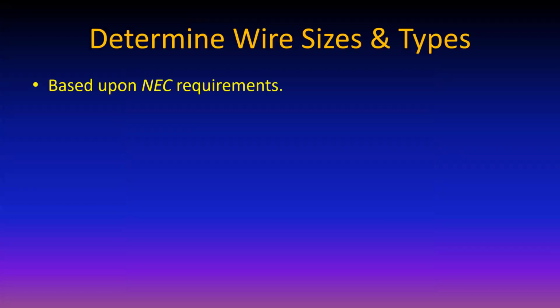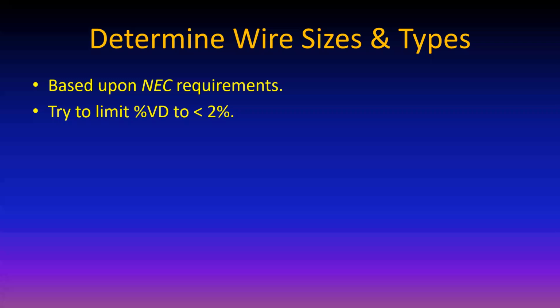Okay, wire sizes and types. And again, I'm going to click through this relatively quickly. National Electrical Code spells it all out. It's nice if you can limit the voltage drop to less than 2%, but in general, NEC allows 3%. But it's not that difficult to limit your voltage drop to 2% because oftentimes you've got multiple conductors in a warm conduit, so you have to derate. So you'll be using bigger than usual conductors oftentimes. So being less than 2% is almost always the case, whether you tried for it or not, in a residential.